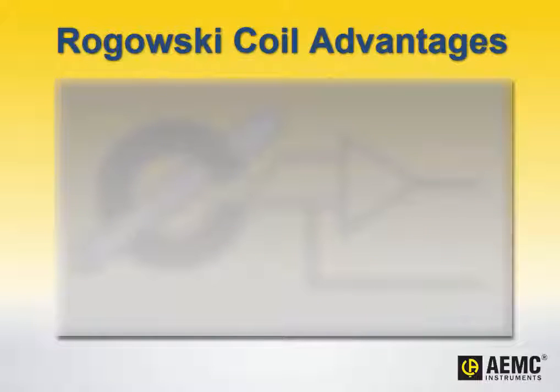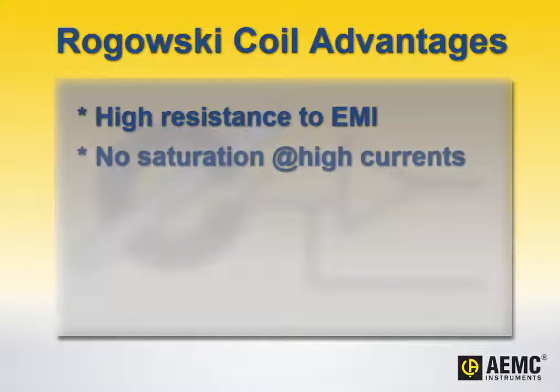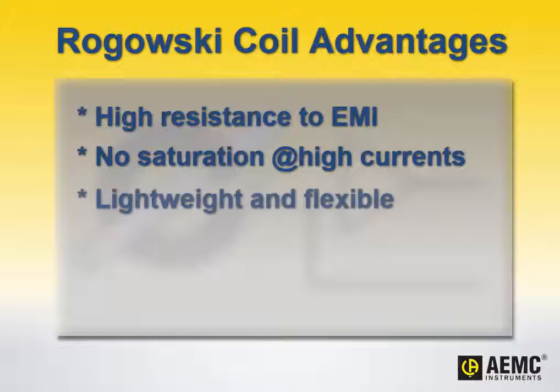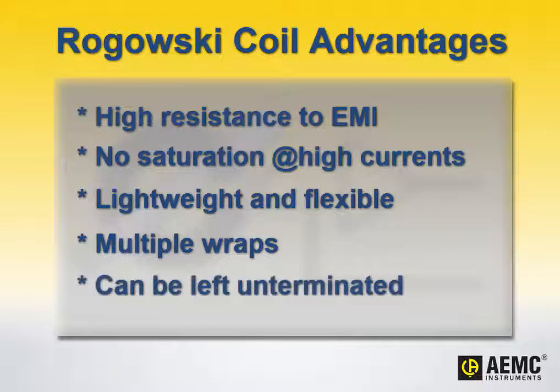Rogowski coils offer several advantages over other probe types, such as iron core, Hall effect, and flux gate. For example, they provide high resistance to electromagnetic interference, and there is no saturation when measuring high currents, ensuring the probes are subject to very little heating. They are lightweight and flexible. The probes can be wrapped multiple times around a conductor to amplify sensitivity, and they can be left unterminated without being damaged or developing hazardous voltage levels.